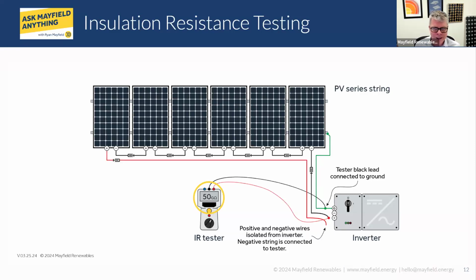Again, trying to do this in a short amount of time is hard, because it's a very long course, so there's a lot that goes into it. One thing to be aware of, because the people on the call are probably very familiar with PV systems: doing a test like this through all these modules, there's some high variability because of things like humidity. If the modules are wet, if the conductors are wet, there's a lot that goes into it. So getting the proper training is about understanding how the tool reacts to those different environmental conditions. A little bit of water on those modules will have a big impact on what that reading is. That's definitely something to keep in mind.